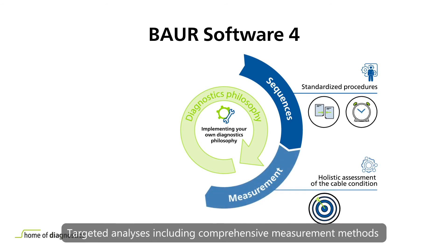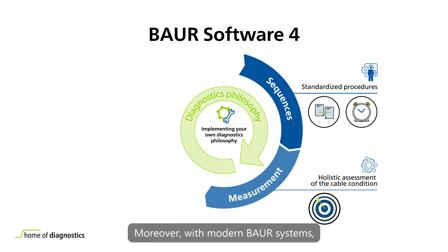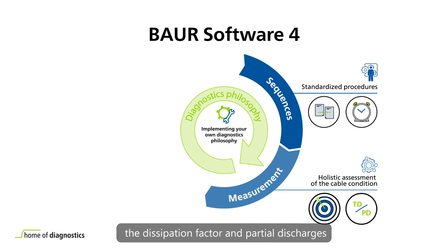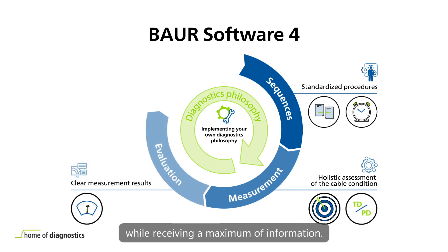Targeted analyses, including comprehensive measurement methods, are carried out for a holistic assessment of the cable condition. Moreover, with modern Baur systems, the dissipation factor and partial discharges can be measured simultaneously with no extra effort. This makes condition assessments much shorter while receiving a maximum of information.